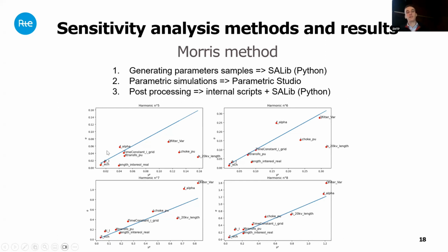So here we can see that for different harmonic ranks we can identify parameters that don't have much influence, such as the sample period and the cutoff frequency of the current loop, and we can identify parameters with a huge influence - for example the reactive power of the PWM filter, the length of the 20 kV cables, and also the equivalent inductance of the inverters.